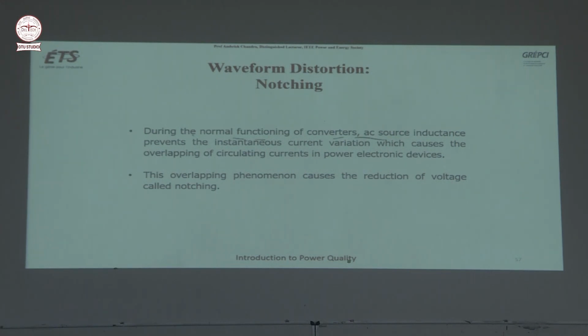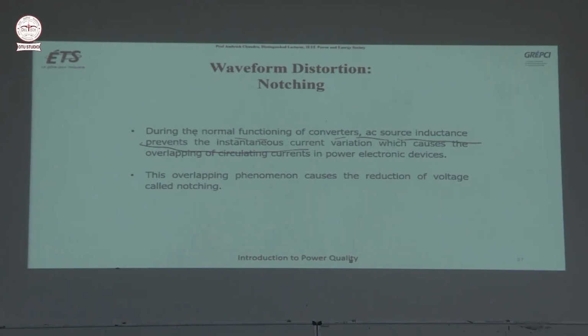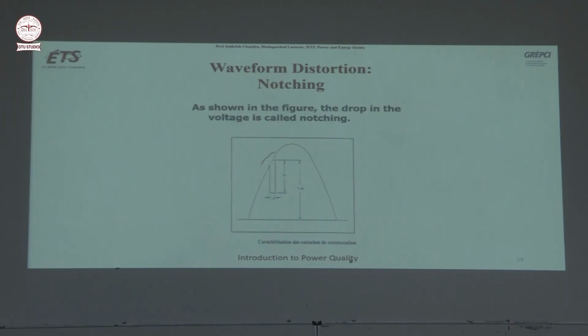During the normal functioning of converters, AC source inductance prevents the instantaneous current, because in ideal condition we say we are not considering any inductance or impedance, so we could see the straight line increase or drop of the currents. But in actual practice, that inductance prevents the instantaneous change of currents. So because of that, there is an overlap. This overlapping phenomenon causes the reduction of voltage called notching. So you can see this is the depth of the notch and this is the width of the notch at some alpha degree when we switch on the thyristor.